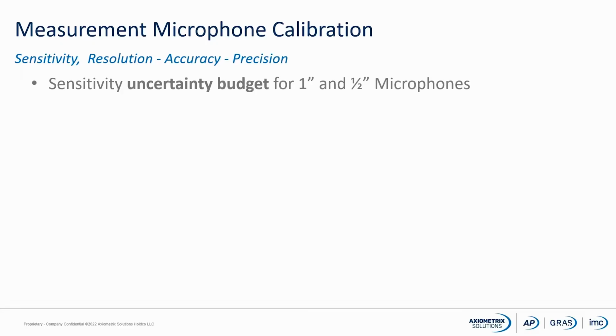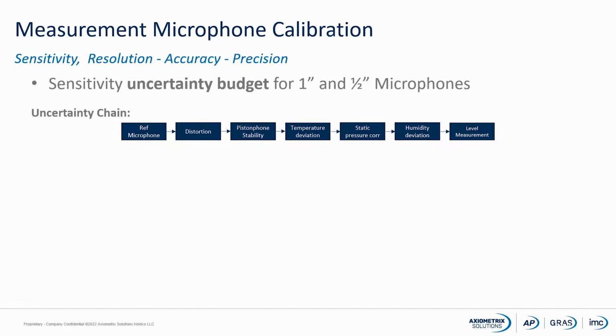When we are doing calibrations, then we also have to take uncertainty into consideration. If we look at an example here for a 1-inch or a 1/2-inch microphone, then the uncertainty chain, when we're talking about sensitivity, could look like this. We have our reference microphone with a certain uncertainty. We have distortion of the microphone. We have pistonphone stability. We have temperature deviation. We have static pressure corrections. We have humidity deviation, and we also have tolerances in our analyzer or voltmeter, whatever we are using for doing the final measurement.